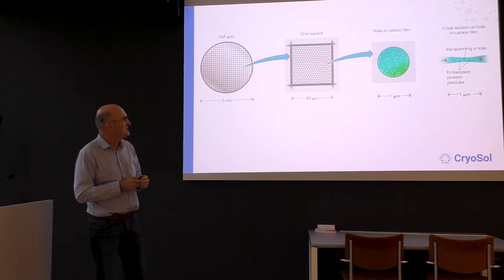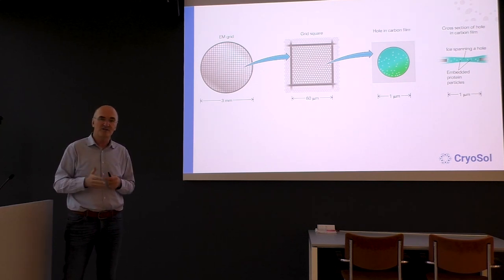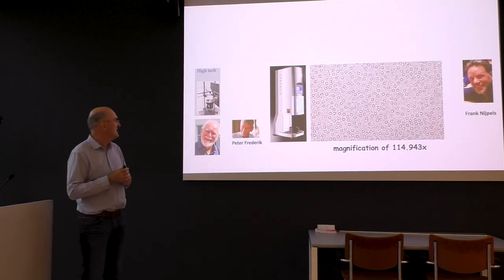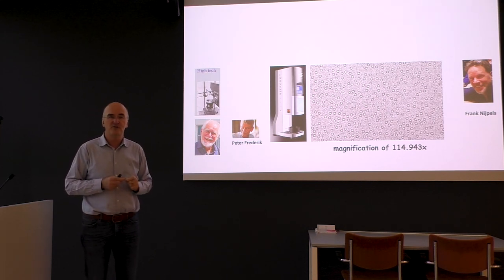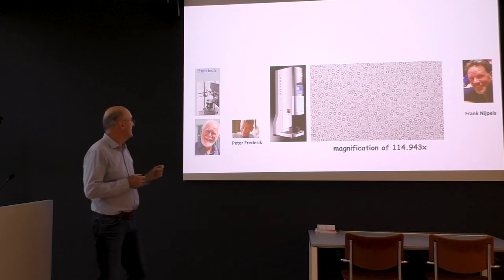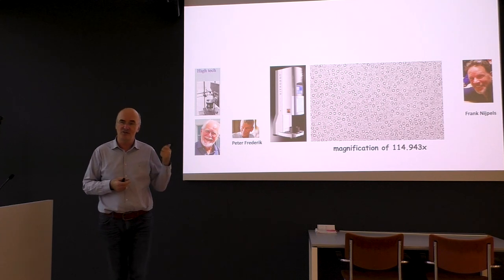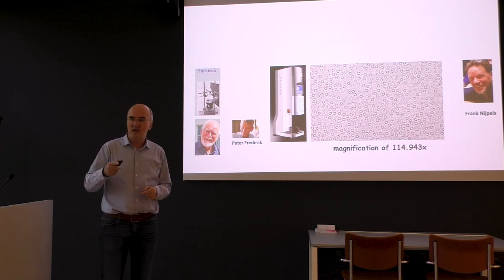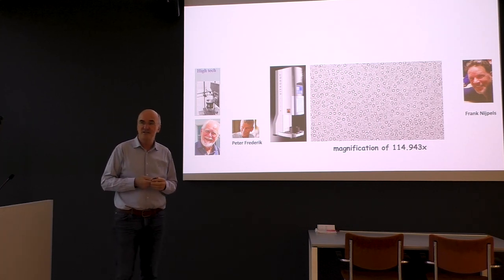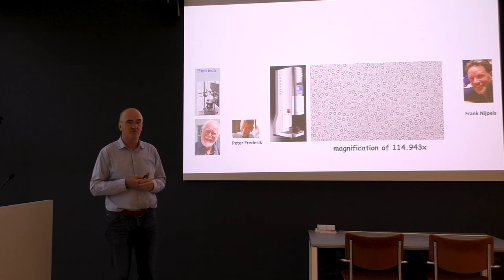Achieving this goal is not trivial. We have been able to do it over the last 10–15 years, thanks to the work done by Jacques Dubochet, who got the idea when he was a group leader at the EMBL to plunge-freeze viruses and proteins in liquid ethane rather than liquid nitrogen in order to get amorphous ice. It was Peter Frederik at that time in Maastricht who got this idea from Jacques and, with the next-door workshop, worked on getting a Vitrobot. Many prototypes followed first, but at the end a product was generated that has now been sold to over 500 labs all over the world.